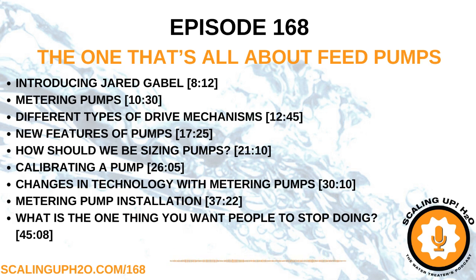So I think what we're seeing now is that I want to be able to remotely get into that pump, get into that application, use the inputs and outputs and the signals that it's picking up around the system to then make good decisions on how I can go about scheduling serviceability or just getting information for reporting, ensuring that the chemical that's being pumped is the right chemistry that's being filled in the tank, because the pumps really don't care what it's pumping, but we do. And so having that feedback remotely and consistently is important, especially in today's day.